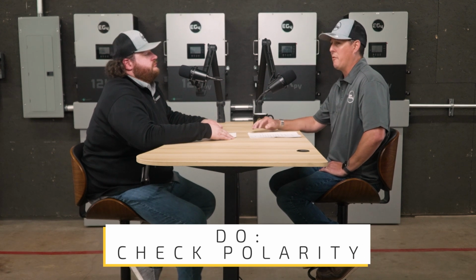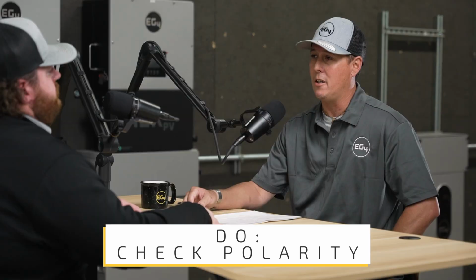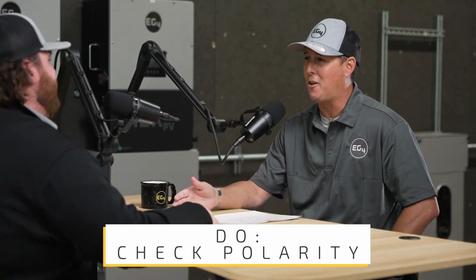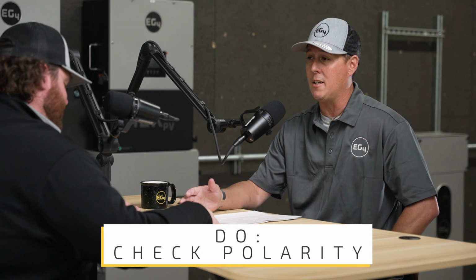That's right. Something else that we see a lot, a ton, is checking polarity. Before you turn on a system, put a voltmeter on it. Check your grid input, check your load output, check your string sizes, right? That's something that we see a lot. I know I've seen it a ton in my career, is you'll get guys that just go by plans, right? Plans are not always accurate. People make mistakes on the design phase or in the system review phase. Put a voltmeter on it, make sure that you're not overloading that DC bus current, and make sure you've got good voltage coming in as well as good voltage going out on that load port or your backed up load panel. So that's a big one.